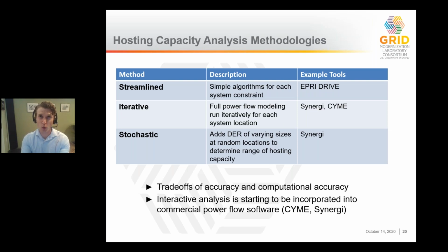And so it's not quite as accurate as the iterative method, which actually performs a full-blown power flow study for every location on the system, very similar to a study a planner would perform during an actual interconnection study process. Iterative is more computationally intensive, so it can take more time to run the scenarios, which becomes more of an issue with very frequent updates over an entire system, where you may start to reach some of those limitations.